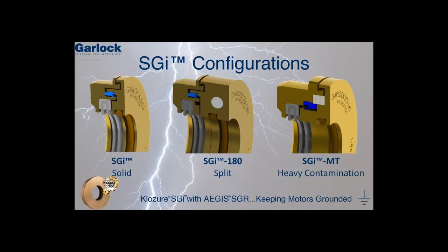Garlock Klozure offers the Shaft Grounded Isolator in three different configurations. First, the SGI is a solid bearing isolator to be used during rebuilds and new installations when the motor shaft is readily accessible. However, when field repairs or retrofits are required, the SGI 180 is a split bearing isolator that can be installed without mechanically disconnecting all downstream equipment, therefore saving valuable time. When heavy environmental contamination is present, the SGI MT is the best option — it uses Klozure's unique microcellular foam to exclude airborne contamination.